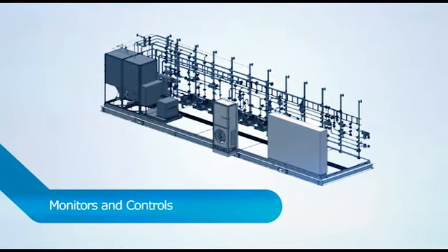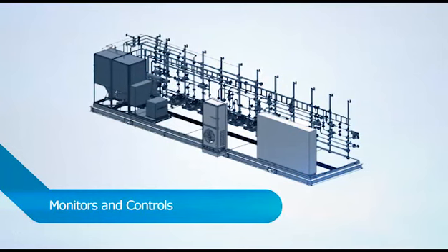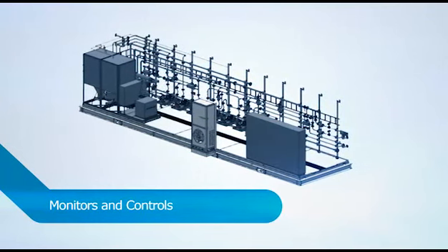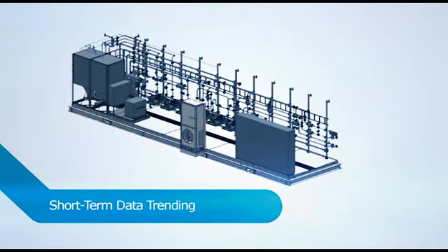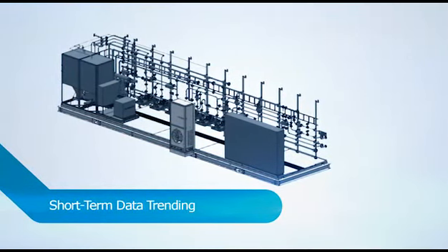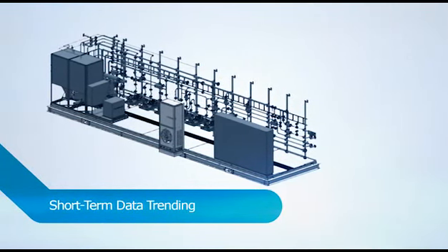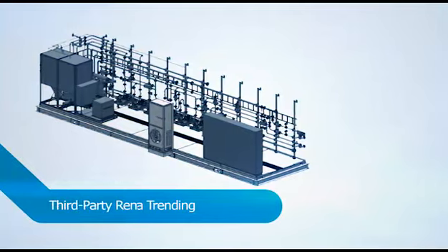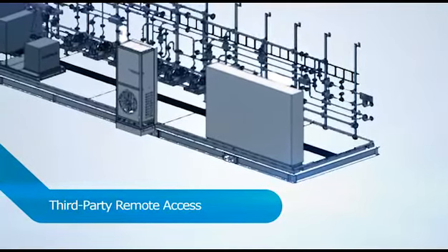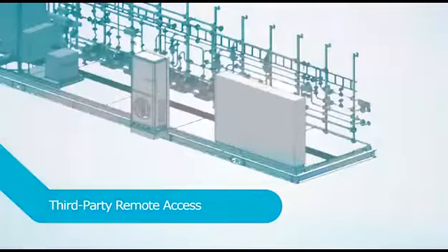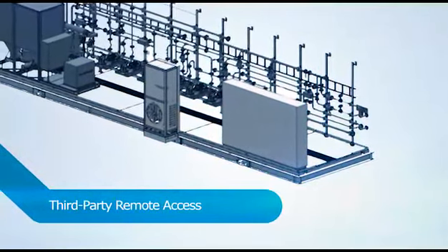The pack monitors and controls all instrumentation and electrical equipment associated with the fuel block. A local HMI permits manual or automatic operation and short-term data trending. Third-party remote access and control is available via Modbus gateway or Ethernet connection.